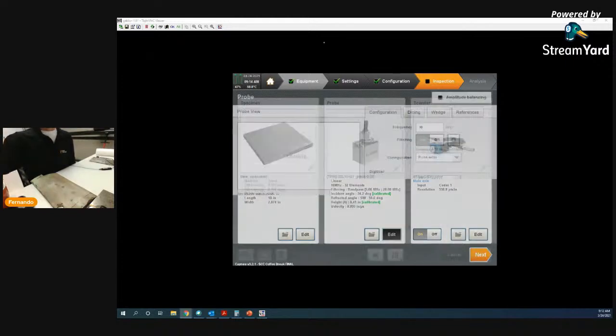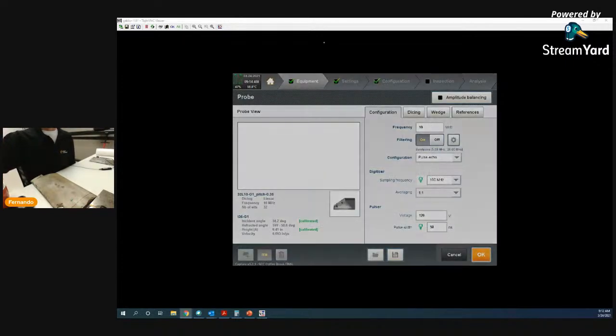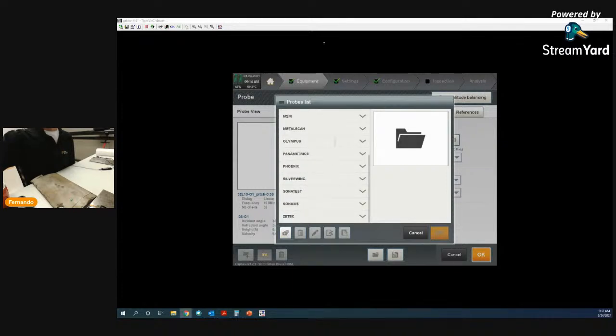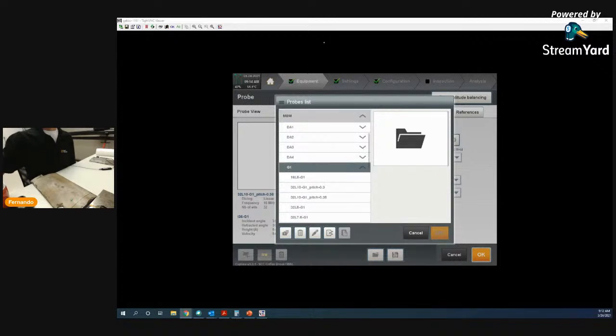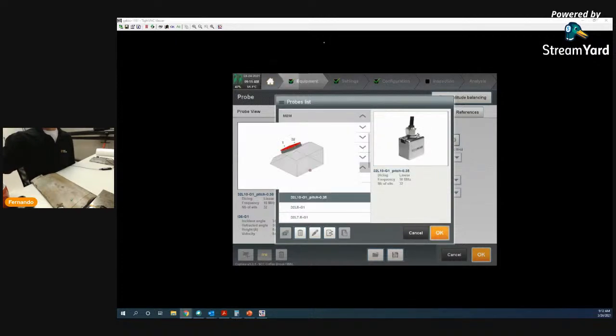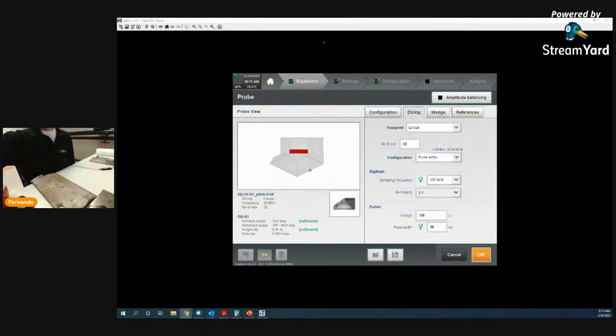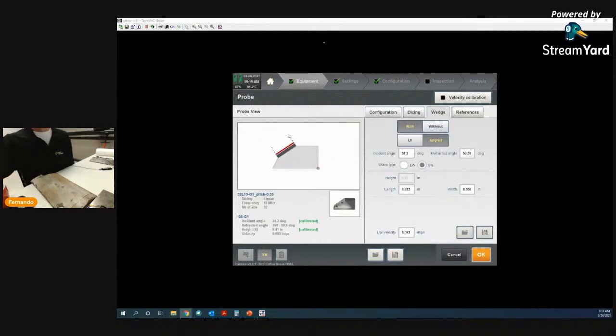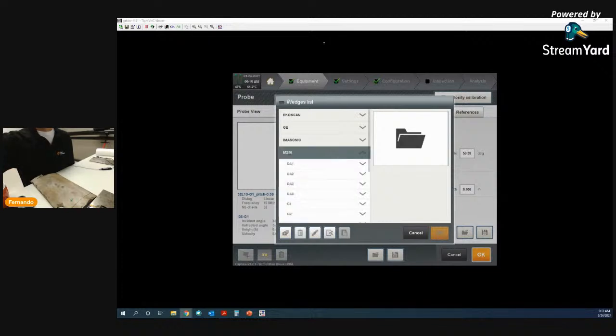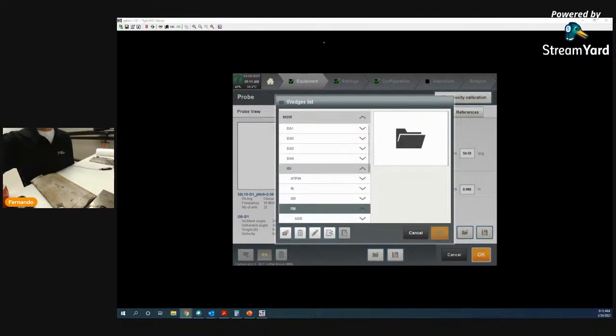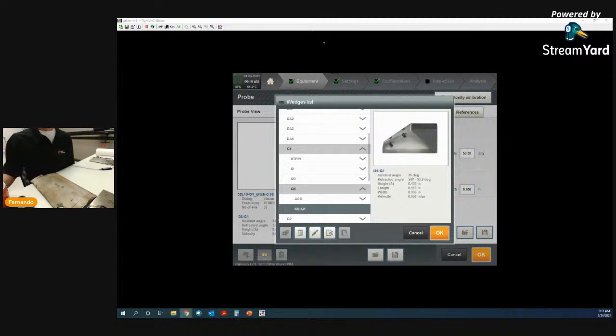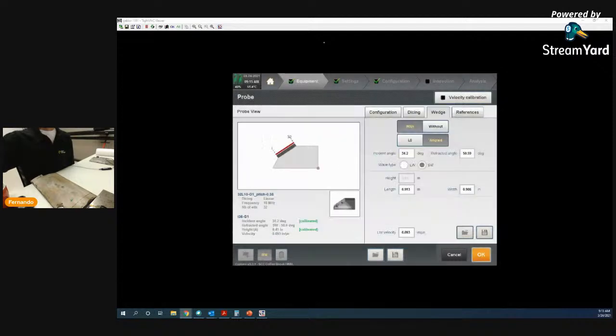In this case here, you can select the probe. You can see on this, there's a list of most of the manufacturers that are out there in the industry that manufacture probes. So right now we're using the M2M G1, and it's a 10 megahertz probe. So you can go through the list, so there's no guessing what the parameters are. They're already inputted. So you have the wedge, and I can input the wedge, same thing. So you have M2M. I'm using a G1, I36, and the I stands for incident angle 36. So I hit OK, and then it puts the parameters for that.